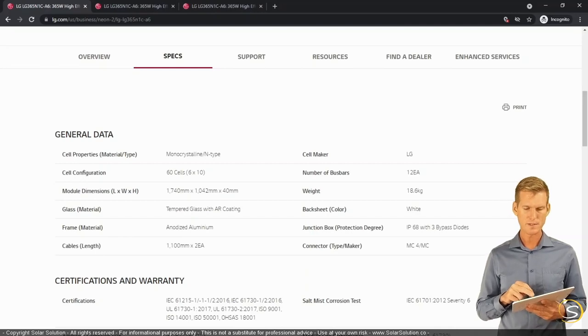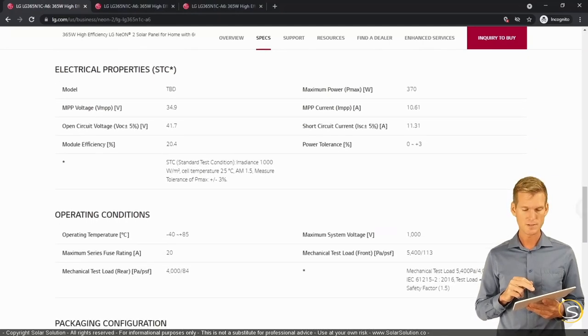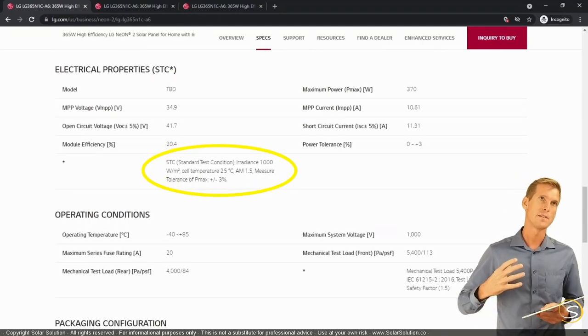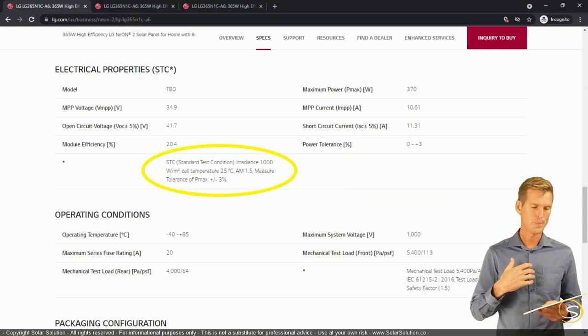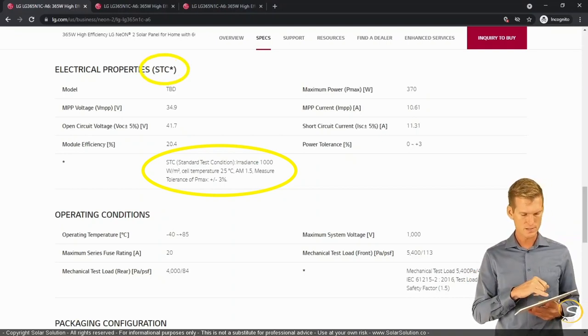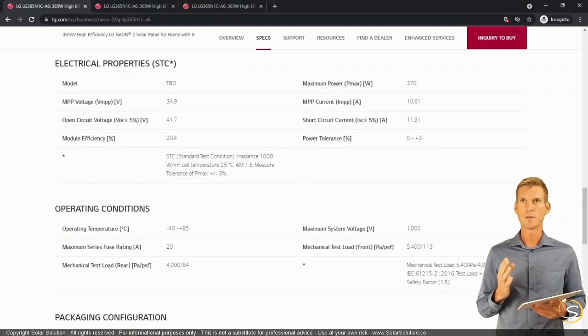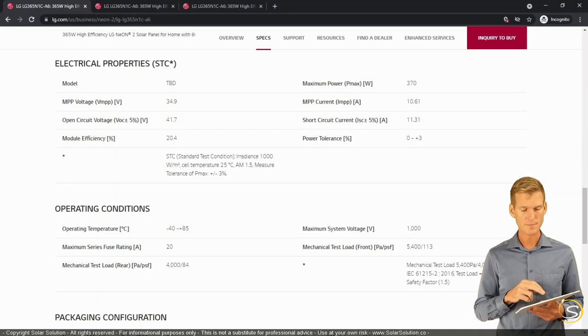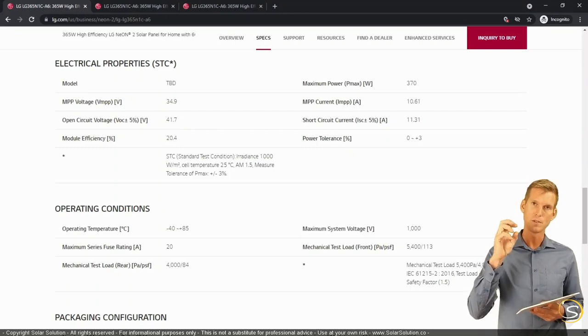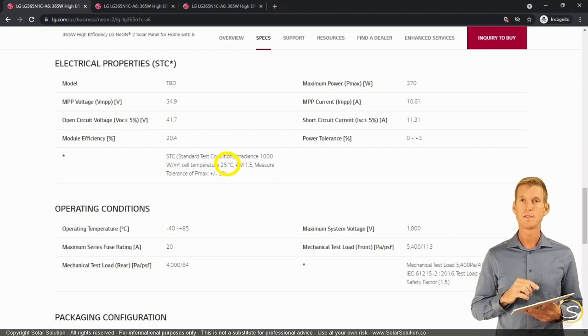So here we are at the electrical properties of this particular model. And it's tested under STC, under standard test conditions, which is quite interesting. So STC is a set of conditions under which you can test the panel. And they will tell you, well under these conditions, if we test in such a way, these are the results. Which is quite important because you can see that they're testing it under an irradiance of a thousand watts per square meters, which is totally possible in real life, but it is relatively high. So depending on where you are in the world, it can be a little bit lower or higher. And the STC works with a cell temperature. So they assume that the cell temperature is always the same. And this is how they test the module. Let's say 25 degrees Celsius, which is 77 degrees Fahrenheit.